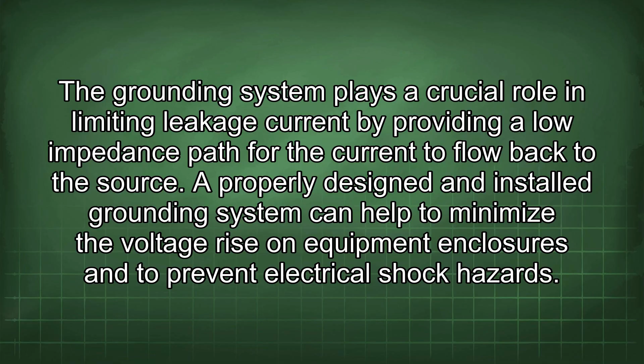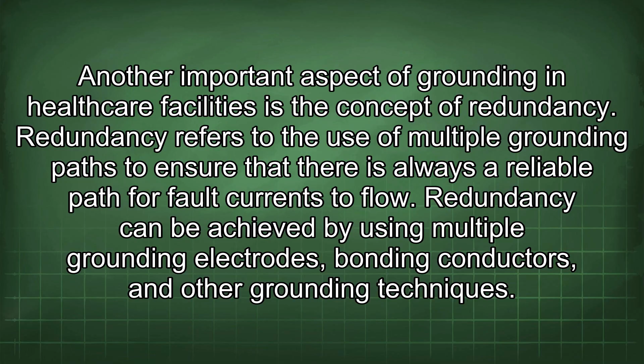Another important aspect of grounding in healthcare facilities is the concept of redundancy. Redundancy refers to the use of multiple grounding paths to ensure that there is always a reliable path for fault currents to flow. Redundancy can be achieved by using multiple grounding electrodes, bonding conductors, and other grounding techniques. The use of redundancy can help to improve the reliability of the grounding system and to minimize the risk of electrical shock in the event of a fault.